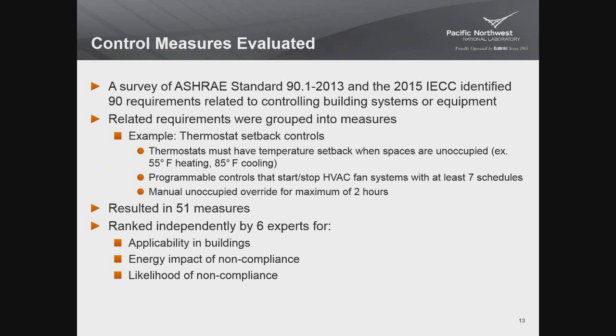So really the very first step was we did a survey of the two model building energy codes for commercial buildings, ASHRAE Standard 90.1 2013 and the 2015 IECC. And we identified all the individual requirements in those codes related to building controls. We ended up with 90 requirements, most of which overlap between the two. There are subtle differences, but not many requirements that are strictly for one and not the other, although there were a few. And then we took those 90 requirements and grouped them into what we called measures, which were simply groups of related requirements. So for example, we have a thermostat setback control measure.